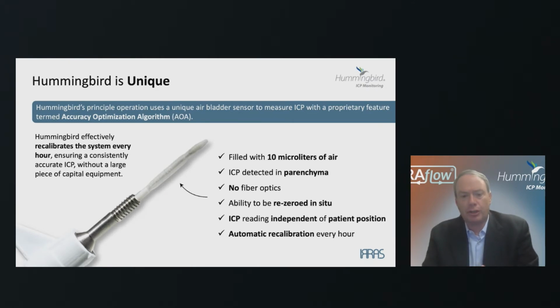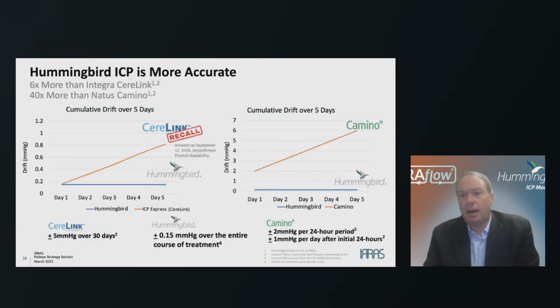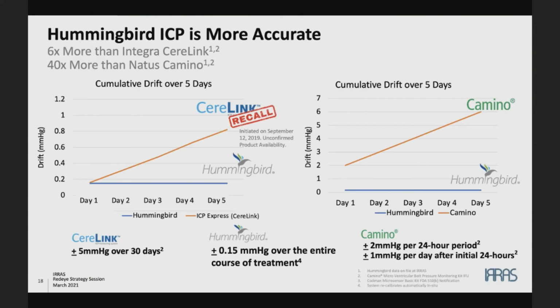The pressure exerted by the tissue is then translated into an intracranial pressure reading and an associated waveform. The system is constantly looking to ensure that the appropriate amount of air is located within that bladder, and as a result it automatically recalibrates itself every hour, ensuring the most accurate ICP reading. That constant recalibration every hour allows Hummingbird to be the most accurate commercially available intracranial pressure monitoring system.